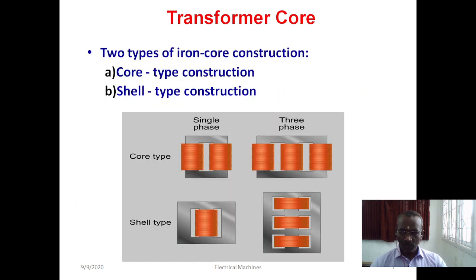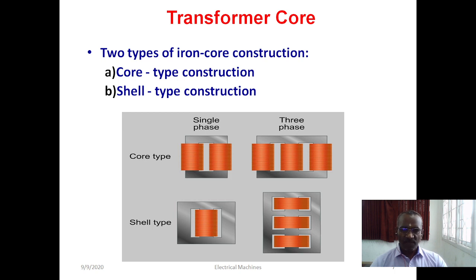First, we will move on to the core. The transformer core has two types: one is core type construction and another is shell type construction. In the core type construction, as you can see in this slide, for single-phase and three-phase transformers, laminated steel sheets are used for making the core. In the core type, the core is covered by the winding — visually we can verify this. The windings are placed on the core limb, and the winding covers the core. That is why it is called core type.